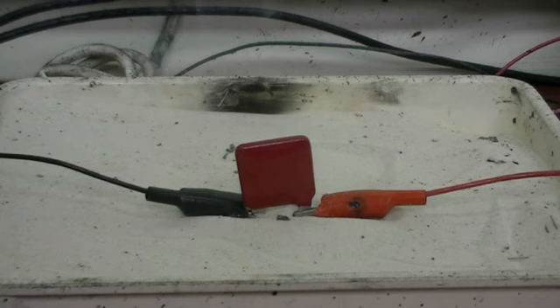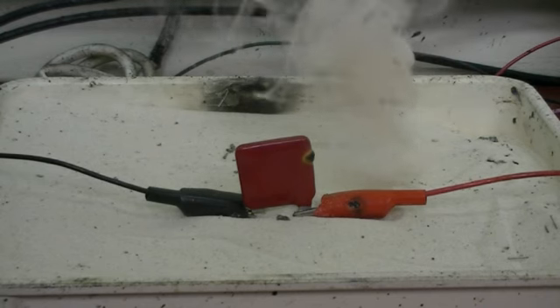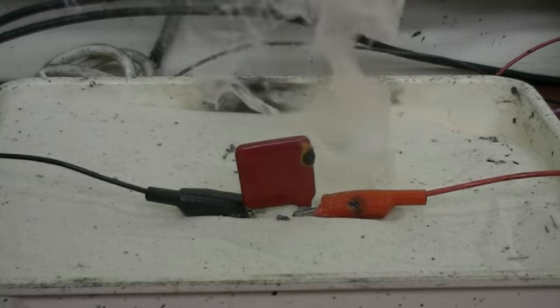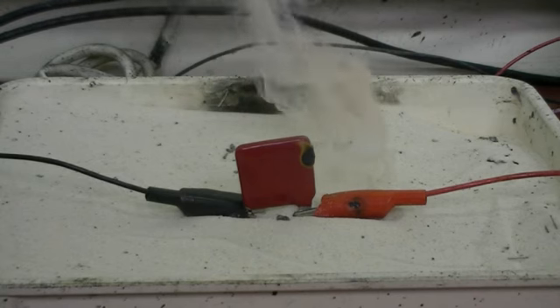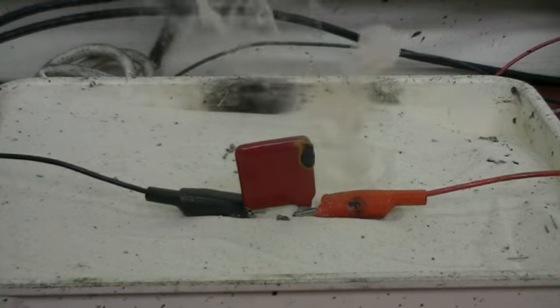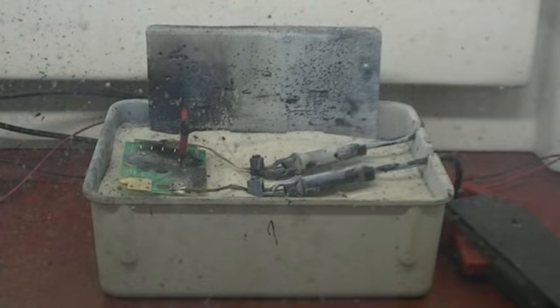Under certain power quality events, MOVs can augment problems through catastrophic failure. As current flow continues through the failed MOV, heat builds up, causing the MOV to rupture and release gas. Older style SPDs containing suppression circuits comprised of multiple paralleled MOVs are prone to magnification of this type of failure. To ensure safe operation of SPDs, MOVs need overcurrent protection and thermal protection that must be properly coordinated to prevent massive SPD failure.